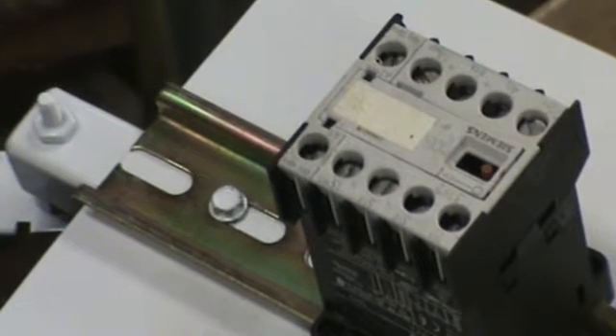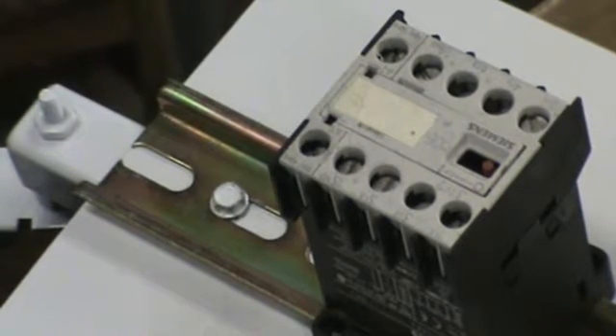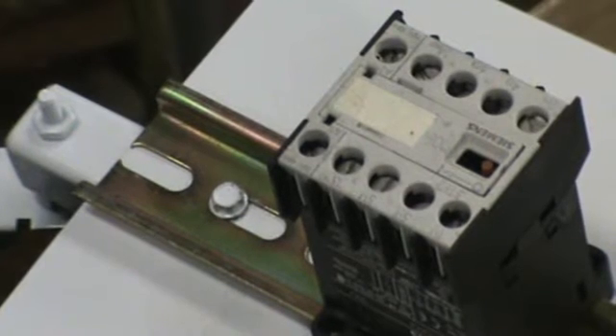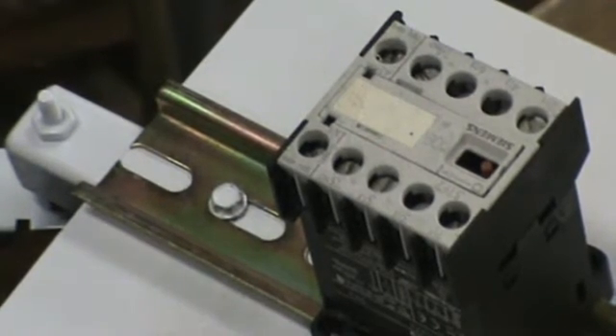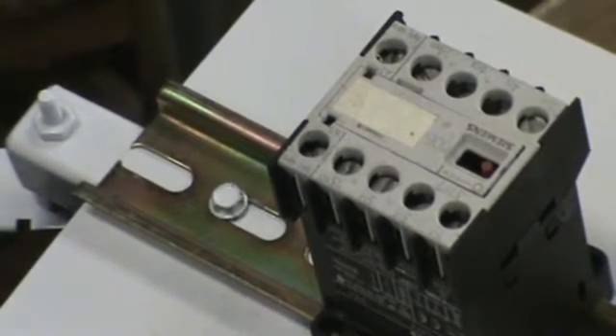Like any good retired electrician — because it is motion control and there are hands and fingers in the way — this contactor here is going to interrupt all AC power to the unit based off of emergency stops. I'll have an emergency stop on the front of the panel along with different push buttons, and I will also have a resident E-stop right on the machine in case I get my stocking cap twisted up in the cutter or something. I can reasonably hit the E-stop and kill all motion and all power to the unit.